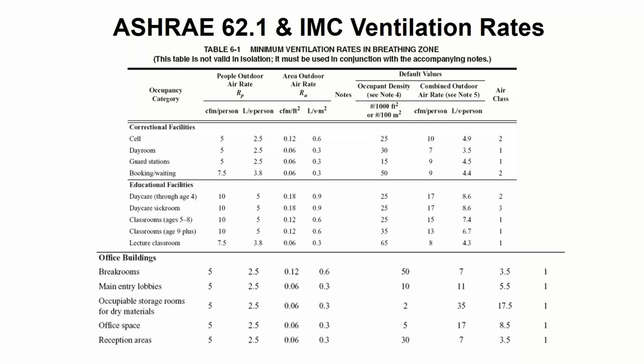And the way that this table works is that, first off, if you're in the United States, just ignore this column. We don't care about liters per second. So that makes it a lot simpler. We get rid of those 2 things. Now I have 2 things to deal with. I have CFM per person, and I have CFM per square foot.